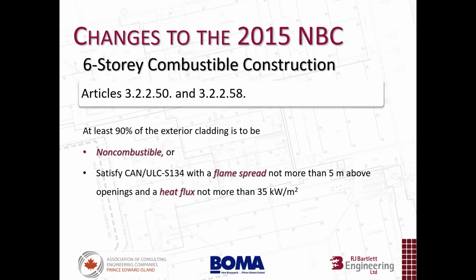Another enhanced design measure for these mid-rise combustible construction is that all of these buildings are required to have non-combustible cladding, or 90% of the exterior cladding is to be of non-combustible construction.